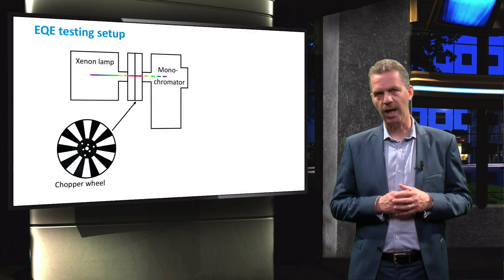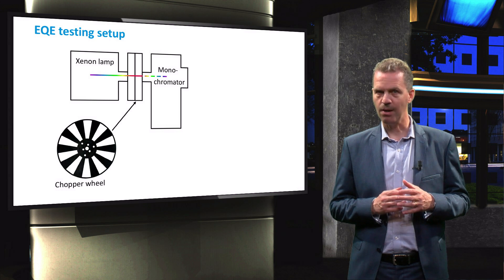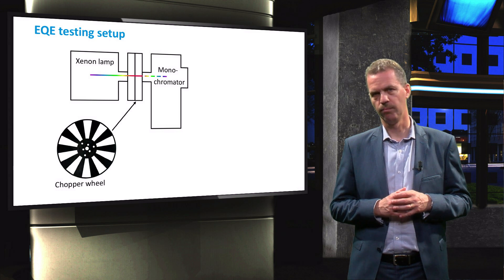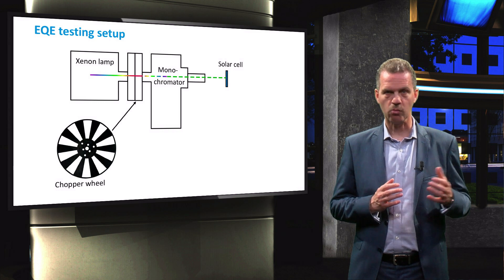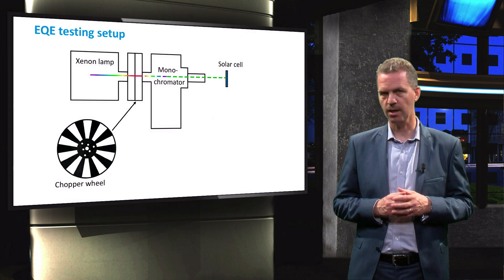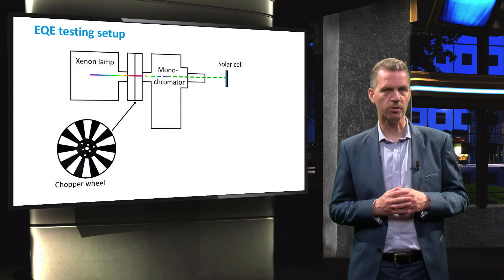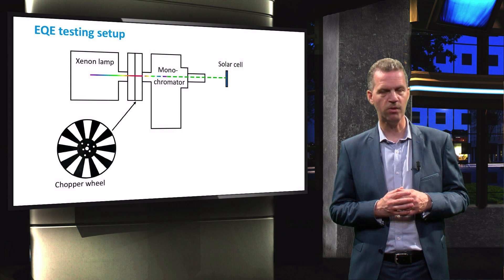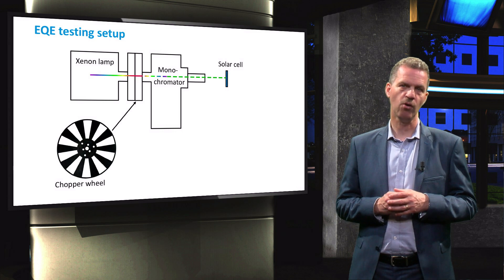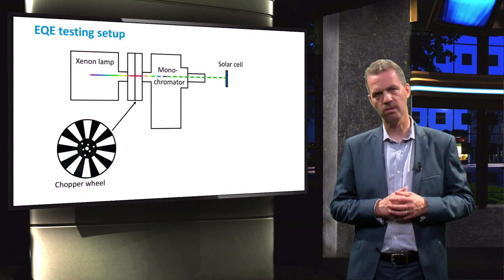The chopped light will enter a monochromator, which is an instrument that can select a very narrow band of wavelengths from the incoming light spectrum. The low-intensity chopped monochromatic light will be focused through a lens system on the solar cell under test. As a result, the solar cell will produce an alternating current signal with a very small amplitude. This signal is converted to a voltage by leading the current through a shunt resistor and measuring the voltage drop.